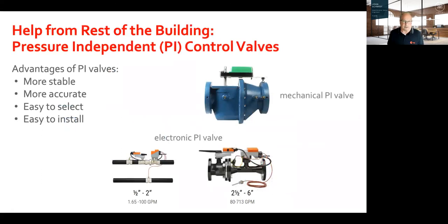Some more help from the rest of the building are pressure independent control valves, or PICV valves as we call them. They come in a couple of styles. There's the mechanical and also the electronic PI valves. The electronic PI valves have an actual flow sensor in them oftentimes, and a supply and a return temperature. More flow does not necessarily mean you're going to get more chilled water out of that coil. There's a limit to that. And they're usually sized a little bit larger. So if you're having some troubles, you can oftentimes increase that flow, but there's a point of no return. So you can actually control to flow rather than temperature, and also be looking at the delta T of each coil. That also can pinpoint areas that might be of concern.